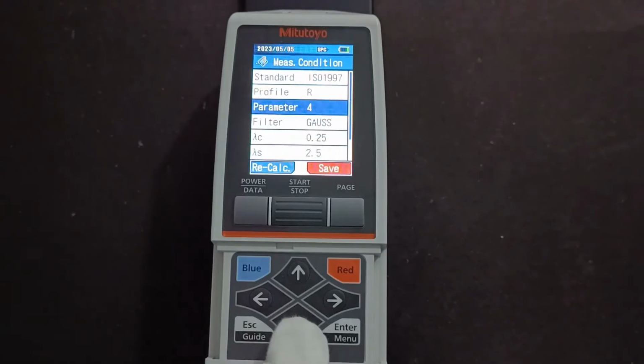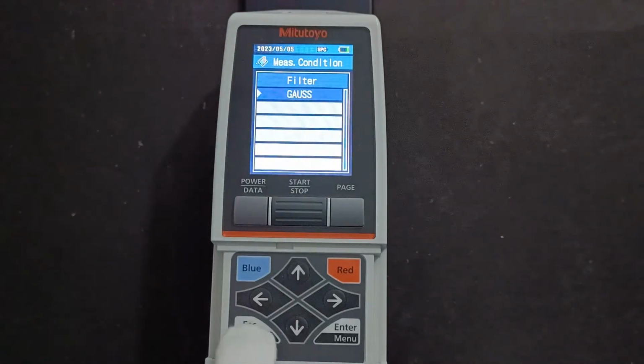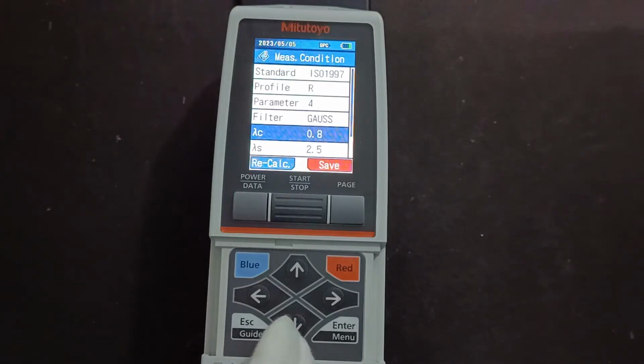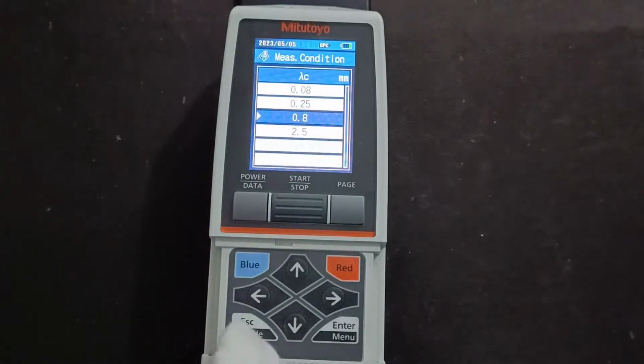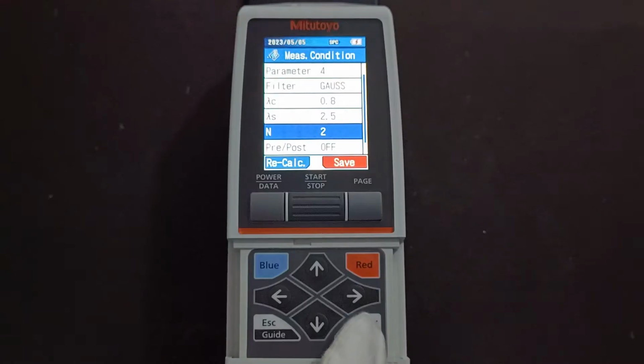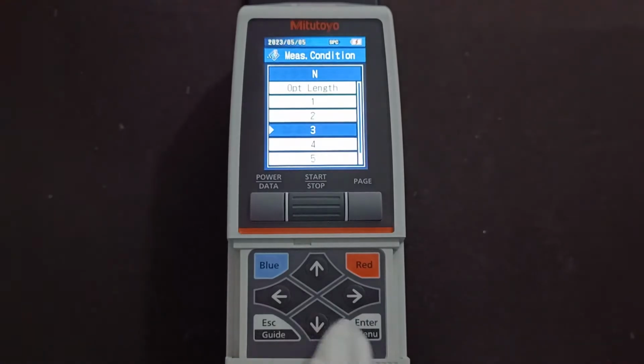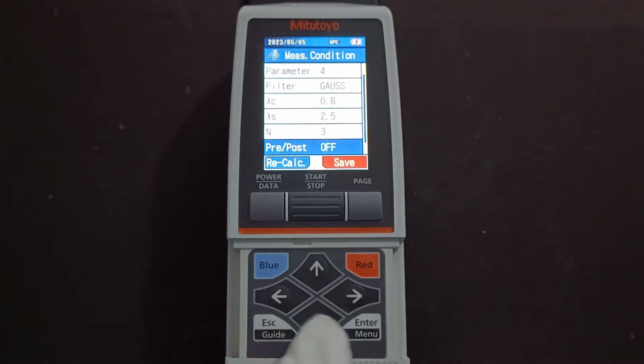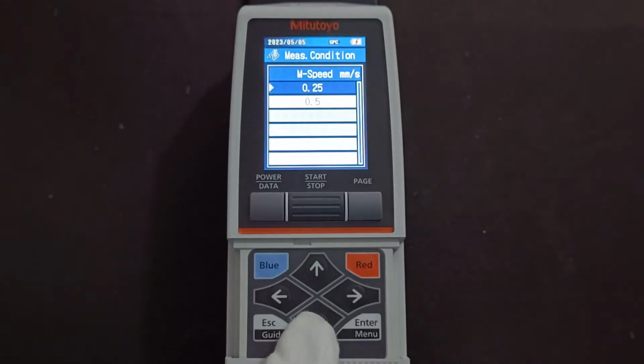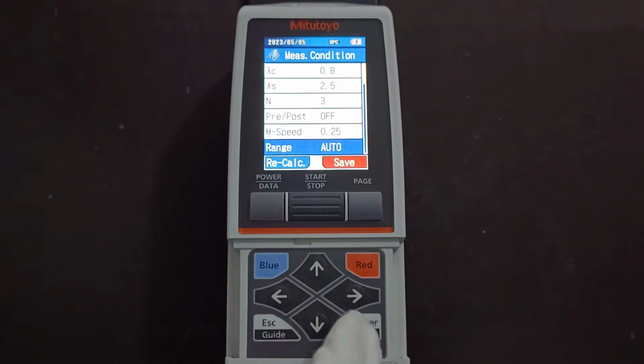Select the required filter. Lambda c is the sampling length, lambda s is the cutoff length. Select the respective sampling length as shown in the table. N is the number of sampling lengths. I have selected 3. Pre or post travel can be turned on or off. M is the traversing speed. I have selected 0.25 mm per second. Select the measuring range as required.